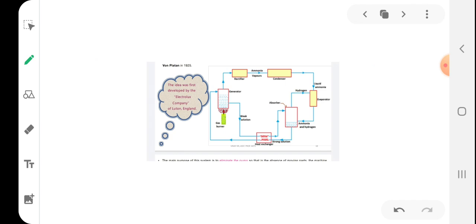So this is the vapor absorption system. You can see the main purpose of the system is to eliminate the pump, right? There is an evaporator, a generator and an absorber, but no pump. In the previous type that we studied, the aqua ammonia system, there was a pump between the absorber and generator, but here there is no pump. Instead there is a heat exchanger, right? The main purpose is to eliminate the pump, so that in the absence of moving parts you can reduce wear and tear and it becomes noiseless.